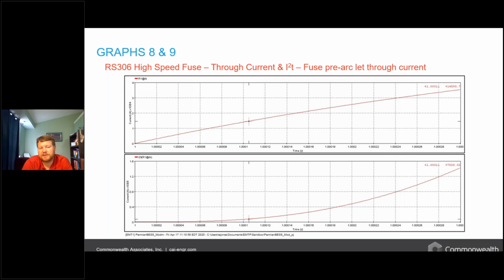So for this particular instance, we looked at it and the fuse is much faster than the DC rise of the circuit. We can see on the bottom part of our graph here that although we have a potential of almost 100,000 amps available, 7,800 amps will be the actual realized fault current, which is much less than the 50,000 amp fuse rating that we have for this application.